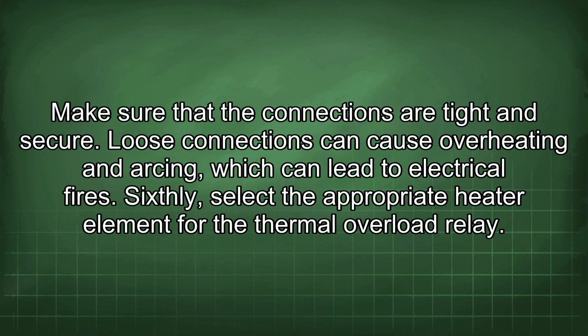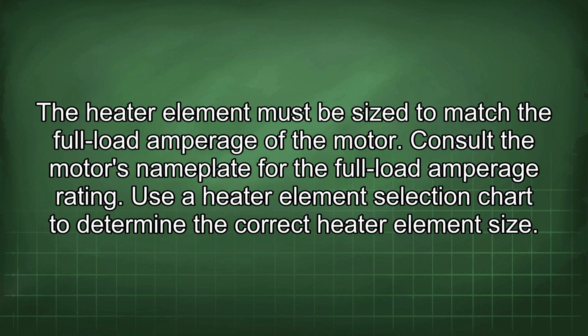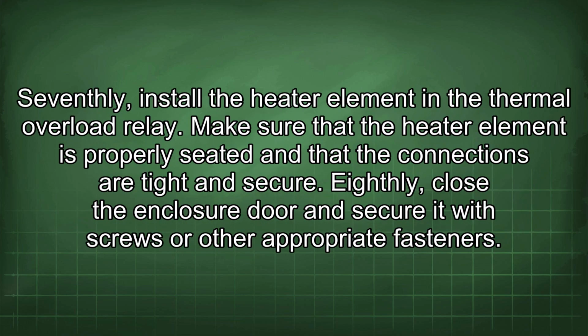Sixthly, select the appropriate heater element for the thermal overload relay. The heater element must be sized to match the full load amperage of the motor. Consult the motor's nameplate for the full load amperage rating. Use the heater element selection chart to determine the correct heater element size. Seventhly, install the heater element in the thermal overload relay. Make sure that the heater element is properly seated and that the connections are tight and secure.